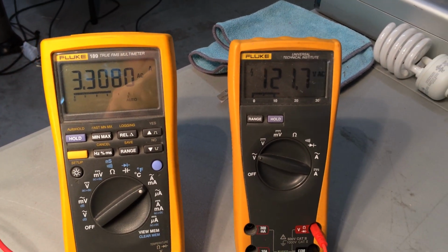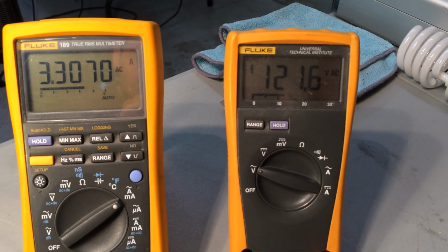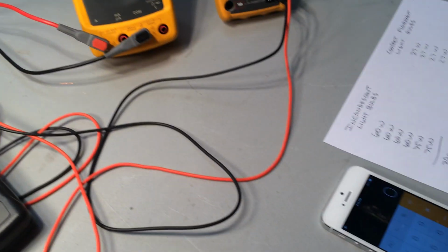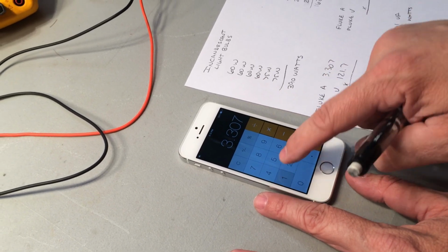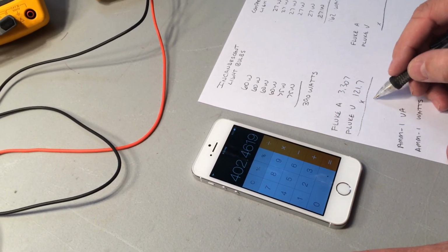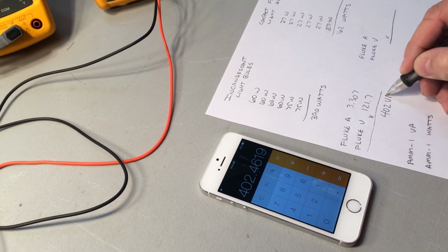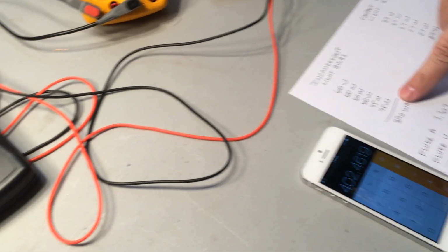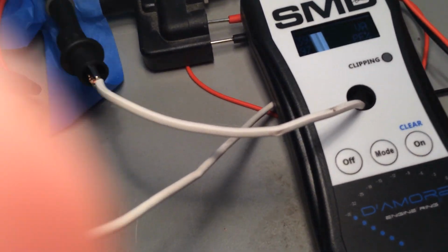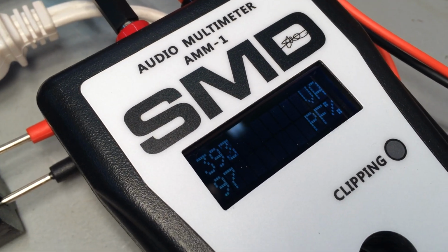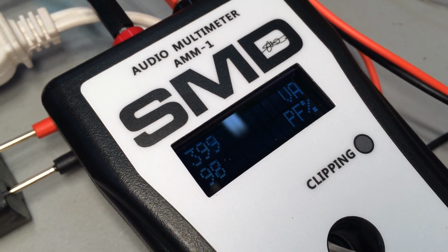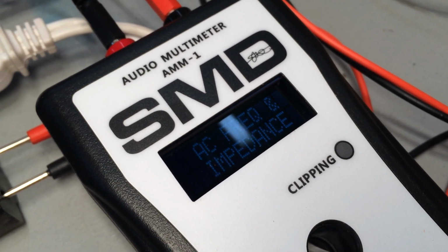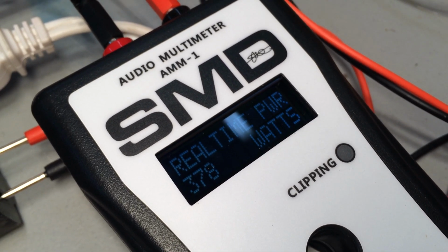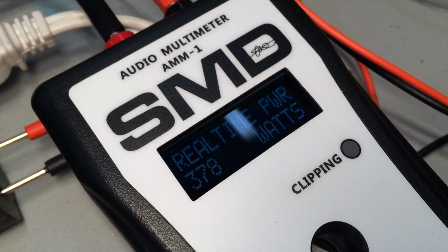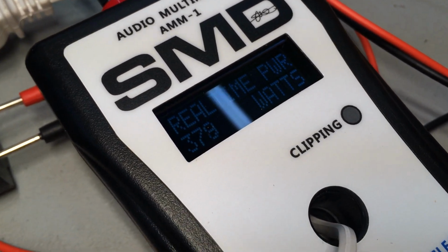Okay, Fluke voltmeter is 121.7 volts. That's just the wall voltage. So I'll take the calculator here. 3.307 times 121.7, 402 watts. But it's not watts, as we know, it's VA. Okay, 402 VA, it's 390 watts, so we're pretty close. Our tool here says, we can read it, bouncing around a bit, it's about 395 to 400 VA, and watts 379. So let's say 395 here and 379.